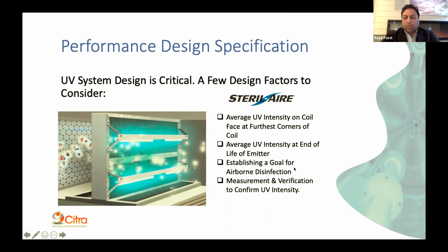For instance, for airborne disinfection, you might want 99% disinfection of the COVID virus on first pass, meaning as the air travels through the air handler a single time, we're getting 99% disinfection. For all these different pathogens, there's an established kill rate table that gives you the UV dosage needed to disable that particular pathogen. Each one has a different level of UV dosage required. COVID actually happens to be pretty easy to disable. Something like molds and fungus are on the other end of the spectrum, requiring a lot more UV energy. So these are systems where you can't just put a blue light in there and expect it to work. It has to be designed properly with the right product.